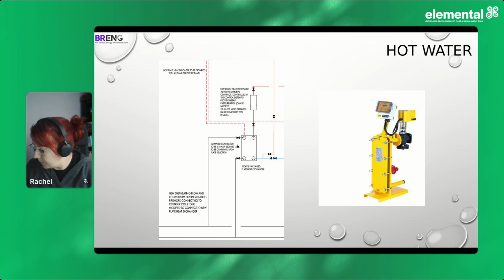Then we get on to hot water. You have to look at hot water completely differently if you're going to go from the current way we do things, which is a big gas-fired water heater, where you can leave your tap running all day and it just keeps replenishing that hot water. So one of the things we need to look at in heating, but especially in hot water, is how do we use the hot water in school? If you're running on heat pumps, you have to have a big storage cylinder to hold your hot water, which is good, but it's also bad because once you've run out of that hot water, you've got to wait a period before the hot water can be replenished, unlike the gas-fired water heaters, which can recover in 10 minutes.